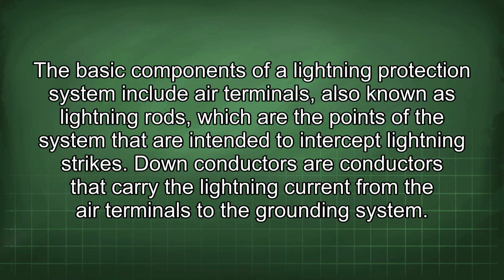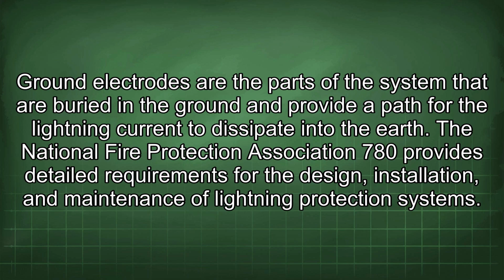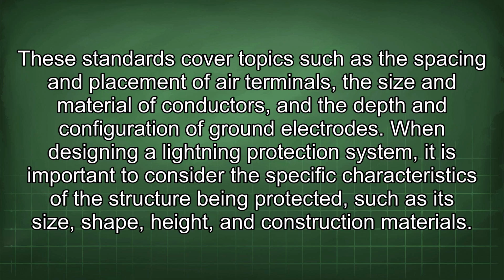The basic components of a lightning protection system include air terminals, also known as lightning rods, which are the points of the system that are intended to intercept lightning strikes. Down conductors are conductors that carry the lightning current from the air terminals to the grounding system. Ground electrodes are the parts of the system that are buried in the ground and provide a path for the lightning current to dissipate into the earth. The National Fire Protection Association 780 provides detailed requirements for the design, installation, and maintenance of lightning protection systems. These standards cover topics such as the spacing and placement of air terminals, the size and material of conductors, and the depth and configuration of ground electrodes.